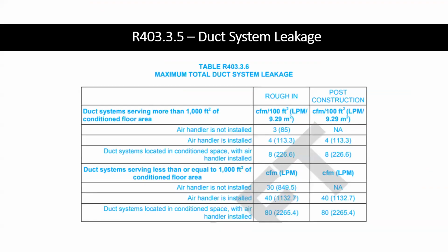So duct system testing has now moved into a table that better clarifies leakage allowed in different scenarios, such as air handler not installed, air handlers installed in testing, it's in conditioned space, or it's in a foam encapsulated attic. But new to 2024, there's now an allowance for smaller dwellings. So anything less than 1,000 square feet, it's really hard to pass that CFM per 100 square feet allowance because you just don't have enough square feet in the calculation to get there.